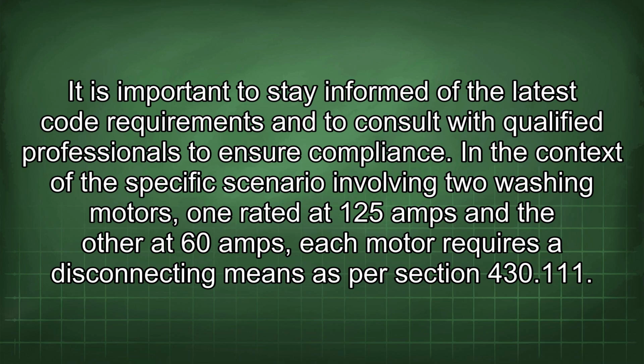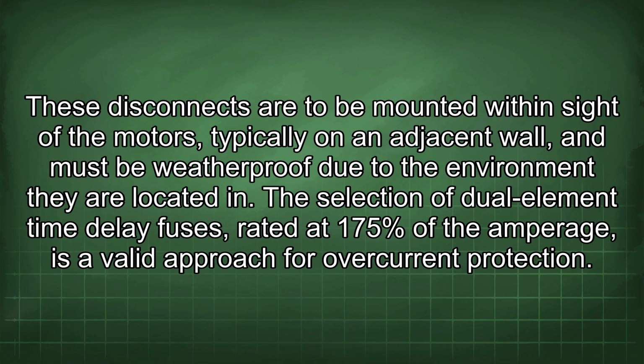In the context of the specific scenario involving two washing motors, one rated at 125 amps and the other at 60 amps, each motor requires a disconnecting means as per Section 430.111. These disconnects are to be mounted within sight of the motors, typically on an adjacent wall, and must be weatherproof due to the environment they are located in.